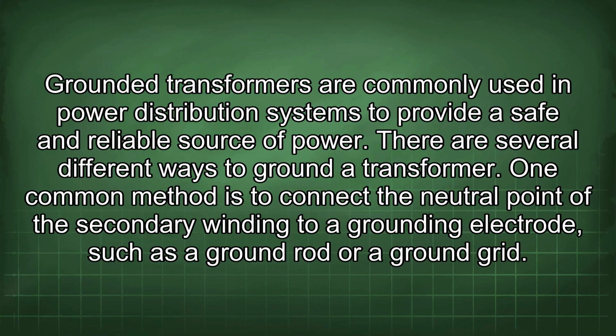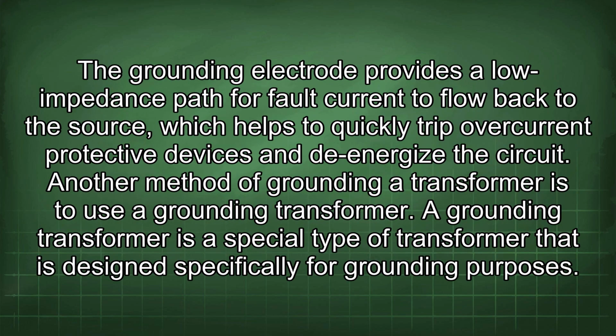There are several different ways to ground a transformer. One common method is to connect the neutral point of the secondary winding to a grounding electrode, such as a ground rod or a ground grid. The grounding electrode provides a low impedance path for fault current to flow back to the source, which helps to quickly trip overcurrent protective devices and de-energize the circuit.